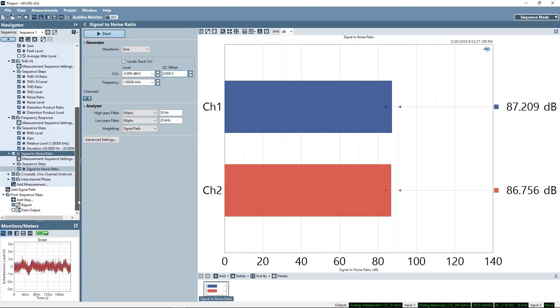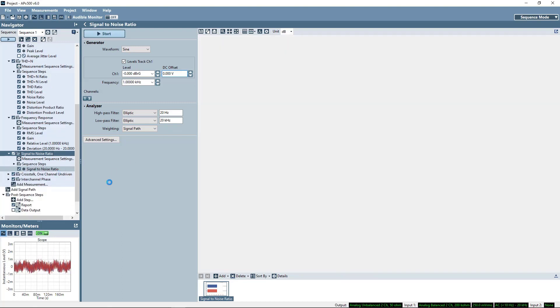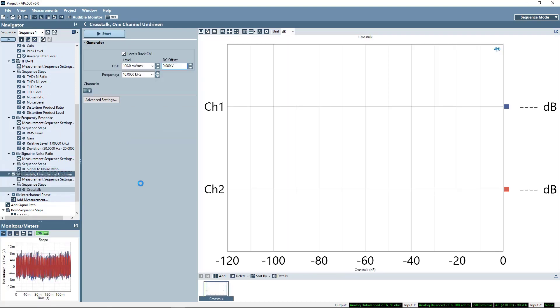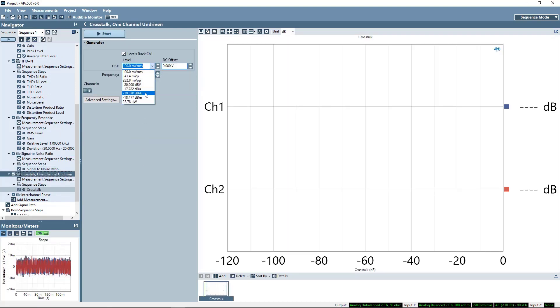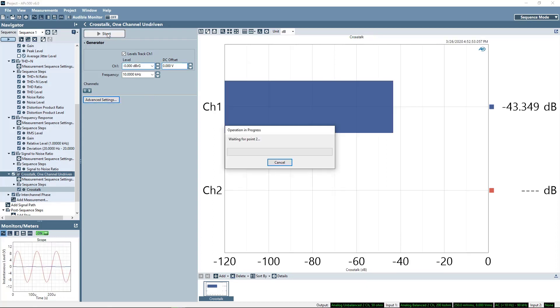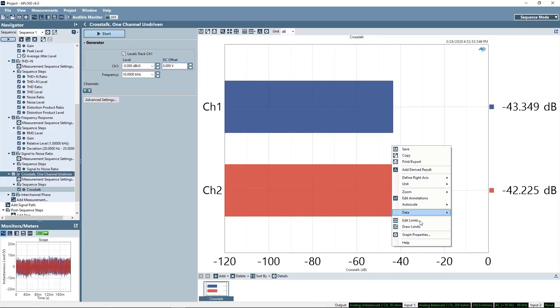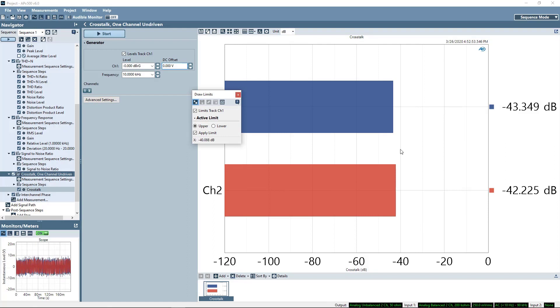Next up is the crosstalk measurement. Crosstalk is the amount of signal leakage between audio channels — in other words, how much of the signal input to channel 1 of the DUT is output on channel 2 of the DUT. I'll add limits here as well.